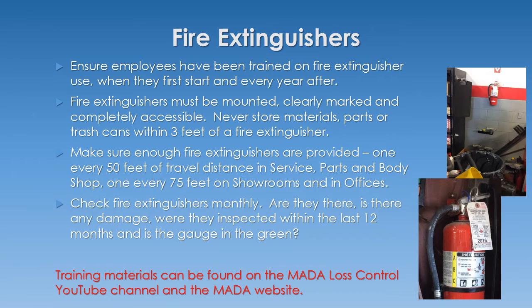Let's talk a little bit about fire extinguishers. Make sure that all employees have been trained on fire extinguisher use when they first start work and then every year after. Fire extinguishers should be mounted, clearly marked, and completely accessible. Never store materials, parts, or trash cans within 3 feet of a fire extinguisher. Make sure enough fire extinguishers are provided: one every 50 feet of travel distance in service, parts, and body shop, and one every 75 feet on showrooms and in offices.